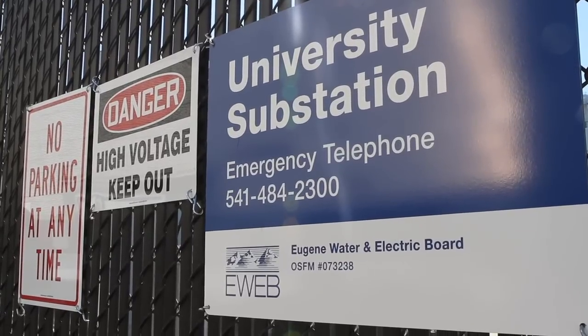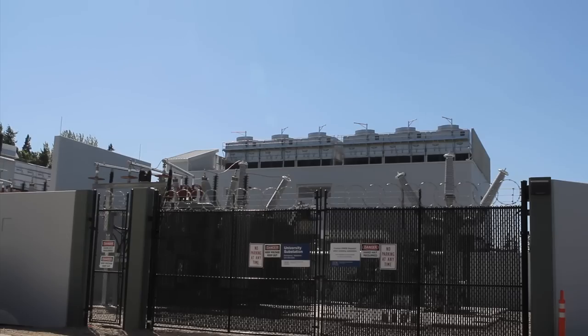The upgrade of the central plant - as we got into the design of it, we discovered that the university had grown beyond what the utility could provide us with the type of distribution system currently serving the campus. So the decision was made to go with a substation rather than expanding the existing grid system. We switched from EWEB distribution to Bonneville transmission.